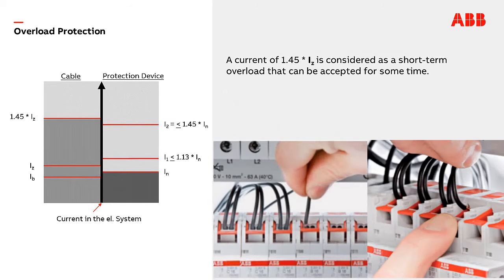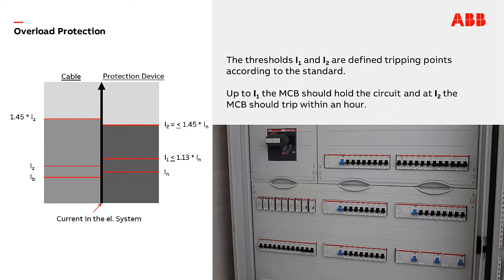A current of 1.45 times Iz is considered a short-term overload that can be accepted for some time. The thresholds I1 and I2 are defined tripping points according to the standard. Up to I1 the MCB should hold the circuit, and at I2 the MCB should trip within an hour.